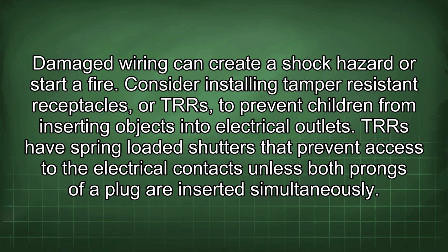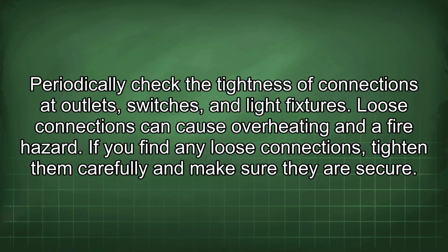Consider installing tamper-resistant receptacles, or TRRs, to prevent children from inserting objects into electrical outlets. A TRR has spring-loaded shutters that prevent access to the electrical contacts unless both prongs of a plug are inserted simultaneously. Periodically check the tightness of connections at outlets, switches, and light fixtures. Loose connections can cause overheating and a fire hazard. If you find any loose connections, tighten them carefully and make sure they are secure.